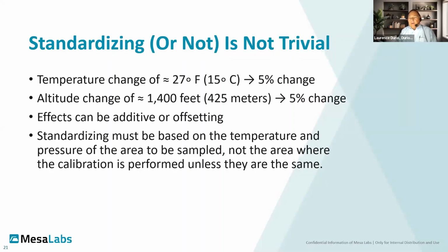So you can have a 25% change between your standard and your volumetric readings, which gives you a pretty substantial difference, easily able to push you into an area where you had concern or did not have concern, as a false positive or a false negative. I do think it's important to recall that standardization must be based on the temperature and the pressure of the area where we're going to sample.